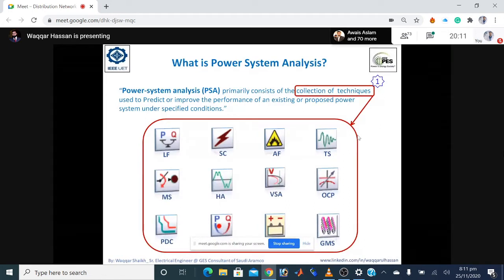One technique, which is the basic study in any power system analysis, is called load flow analysis or power flow analysis. In this study, we are concerned about the steady state voltages on the buses, the currents passing through the branches, the active and reactive power flows, the power factor of the system, and the sizing of equipment like cables, transformers, and breakers. Load flow study takes care of all this.